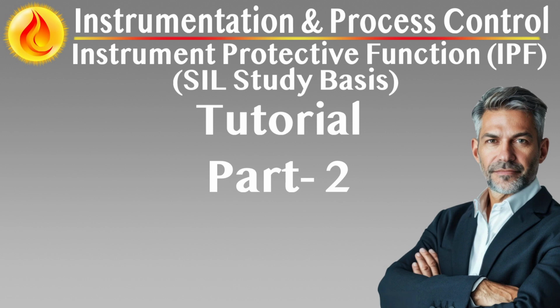Implications for SIL assignment. When synergetic consequences are credible, the highest individual consequence category typically governs the SIL target, but the combined impact may justify moving to the next SIL level. Standard risk matrices may underrepresent the compound nature of the event unless configured to flag synergetic outcomes explicitly. Conservative assumptions must be applied to capture the potential for escalation and reduced operator response time under complex, multi-hazard scenarios.